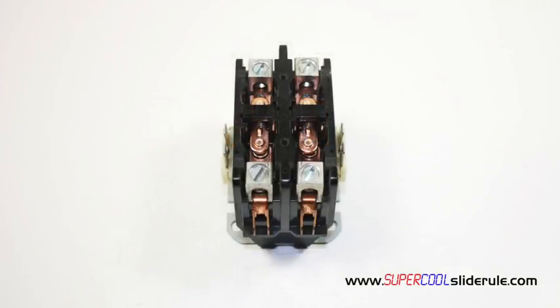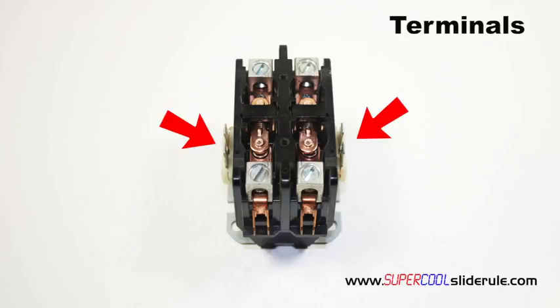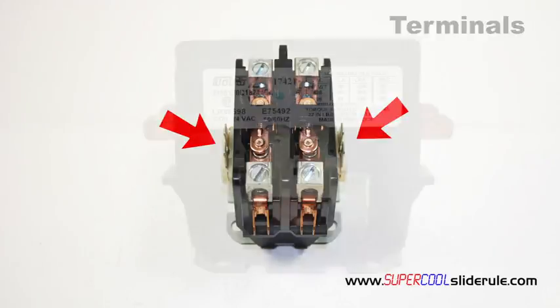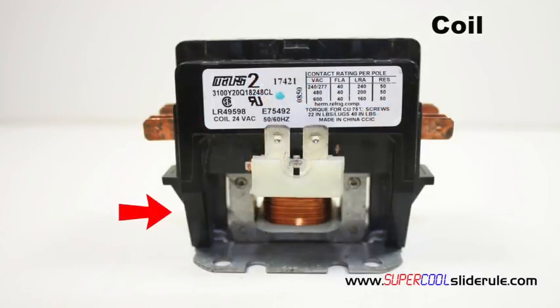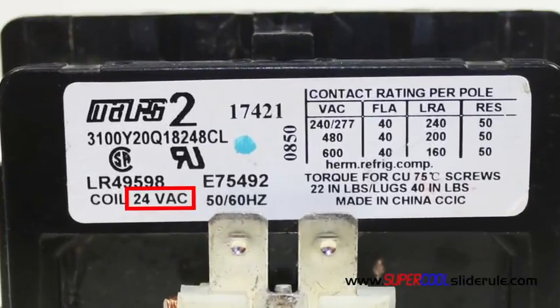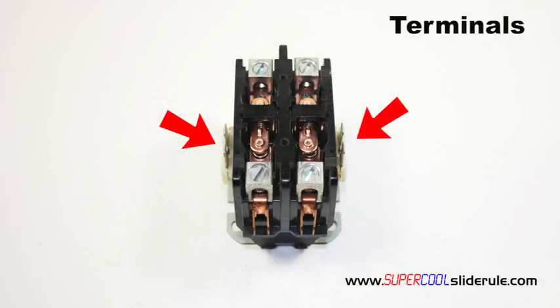To operate the contactor, low voltage is supplied to the terminals located here and here. It is important that the low voltage we supply match the required coil voltage printed on the side of the contactor. In this particular example, the contactor has a requirement of 24 volts AC. Either low voltage wire can be connected to either terminal.